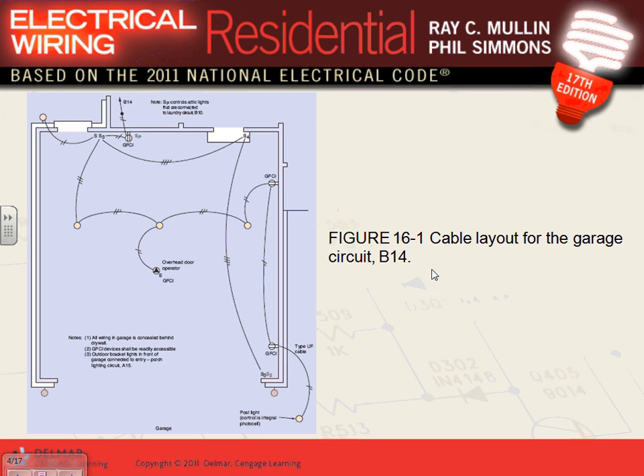So this is to control these lights. I have a garage door opener here. In 2011 NEC, the garage door receptacle, plugged in, as most of them are, cannot be GFCI. The receptacle cannot be GFCI here. It has to be fed through, because it's readily accessible. So keep this in mind. The only way I can make this outlet here readily accessible is if I put the GFCI on the wall. So what would I do? I take the GFCI from here and feed through directly to this receptacle. Okay, so that's basically what they're doing here.